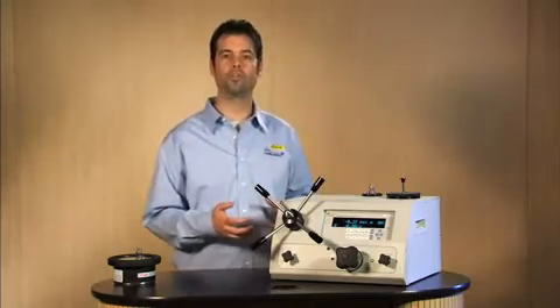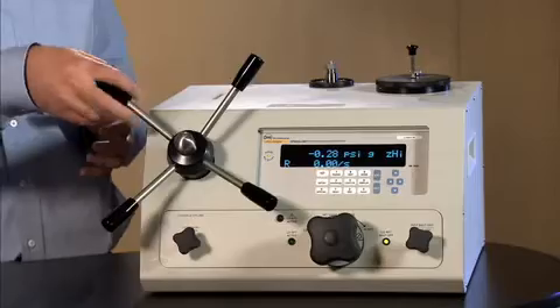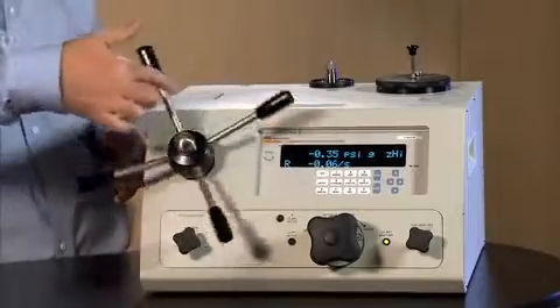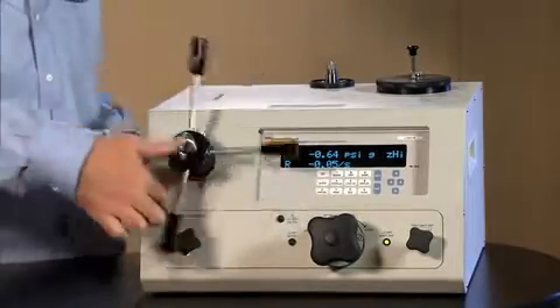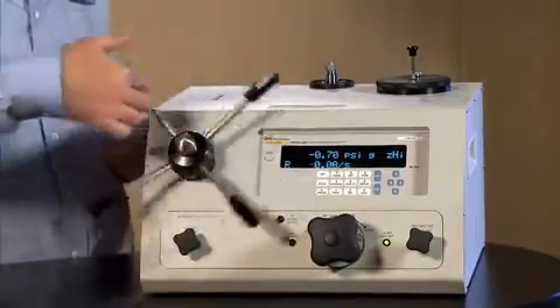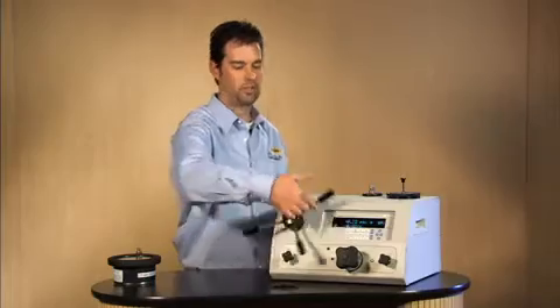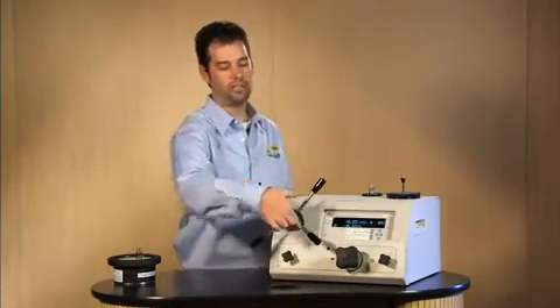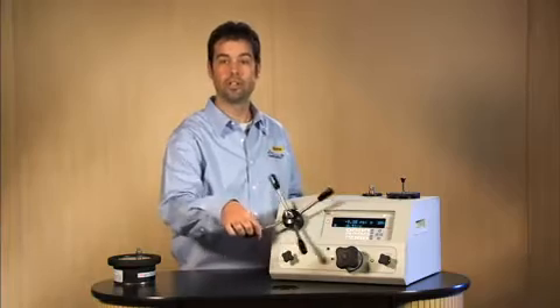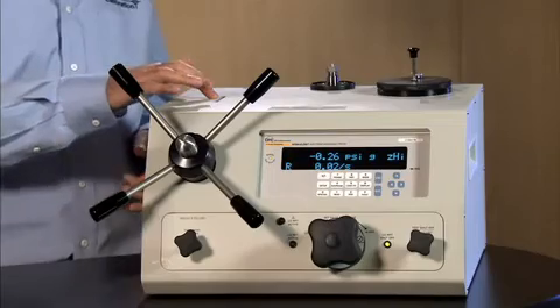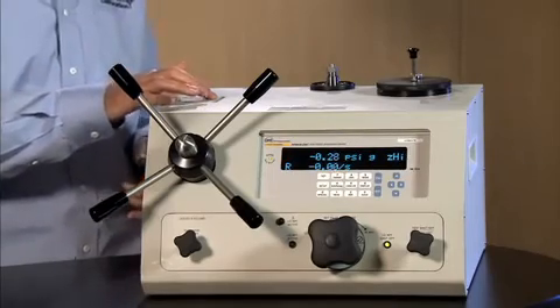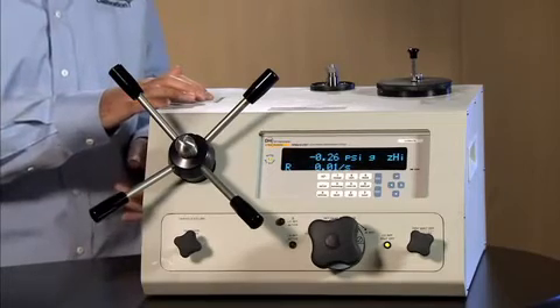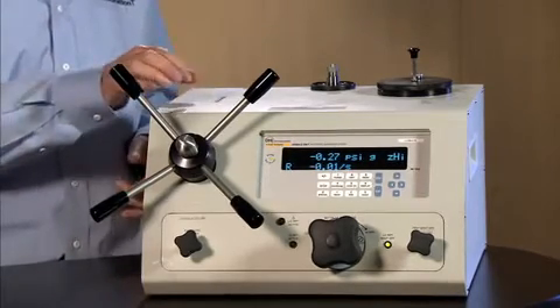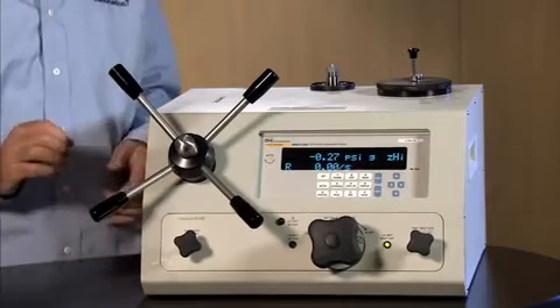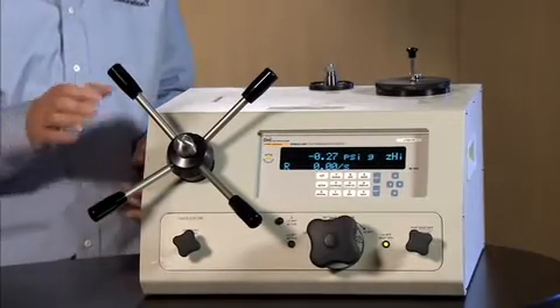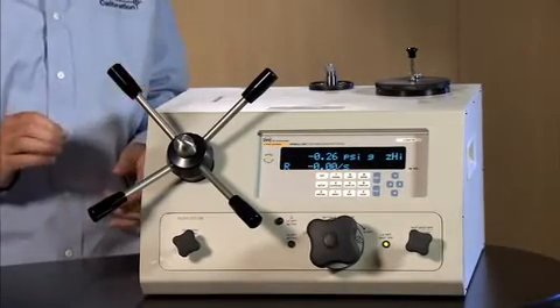To pull that fluid from the reservoir into the variable volume, we can go counterclockwise on the handles. You can see how easy this is. It takes one finger to go back. You can go pretty fast until it stops. There's a variable volume position indication on the top of the electronic deadweight tester, which will give you where that stroke is for the variable volume. Right now, it is backed out all the way.